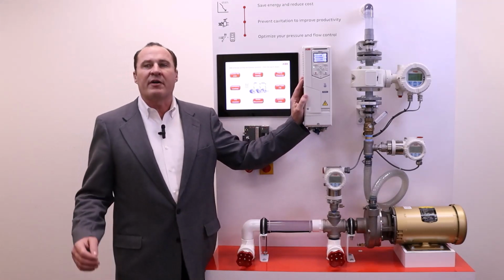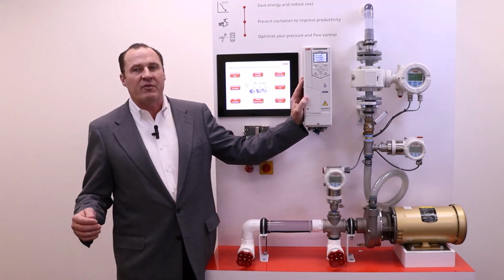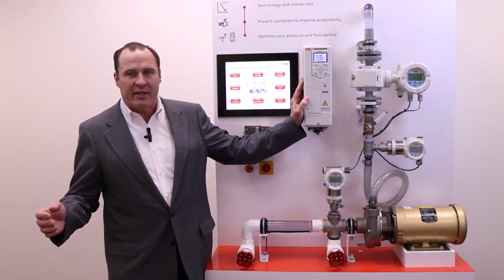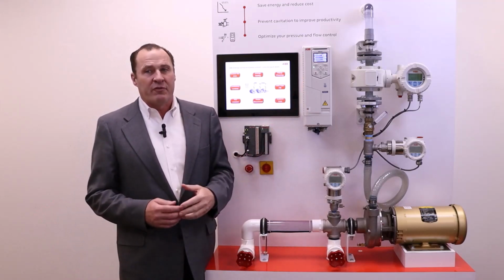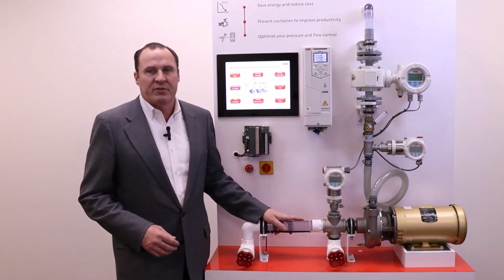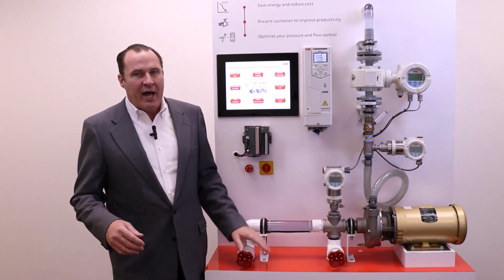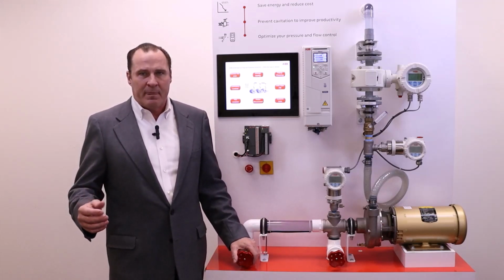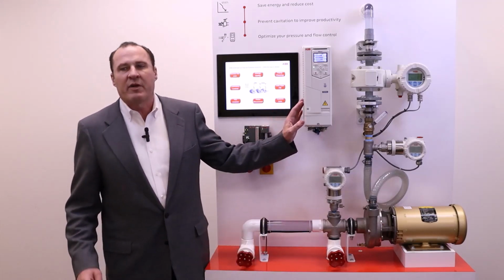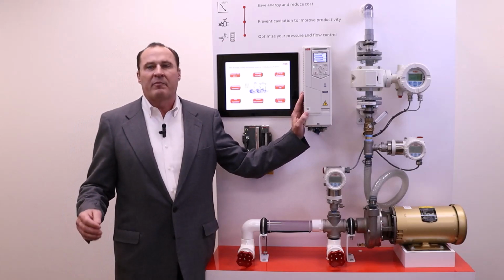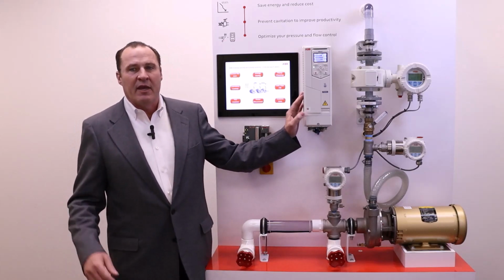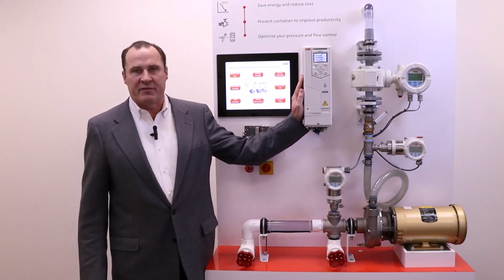Sensorless pump control also works in conjunction with other drive pump protection features like high or low pressure flow protection, pipe rupturing, closed valve or blockage, pump cavitation. Sensorless pump control is one of the many innovative solutions brought to you by ABB and the ACH580 drives family.